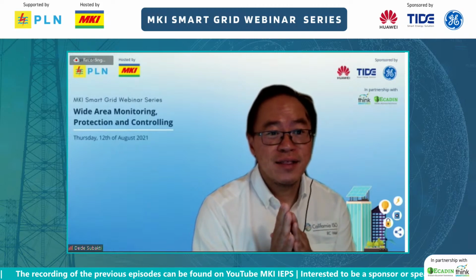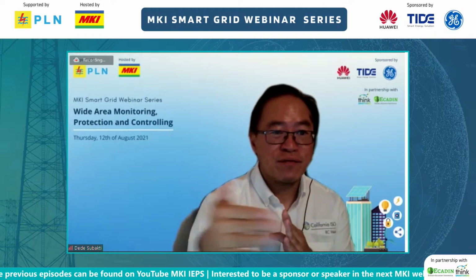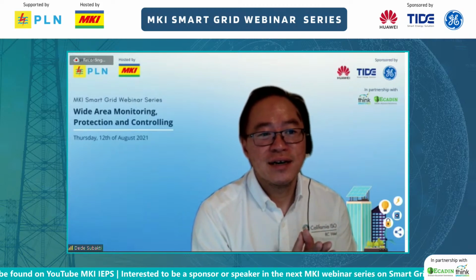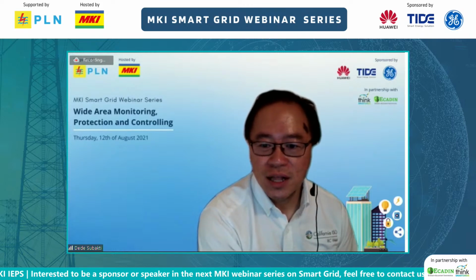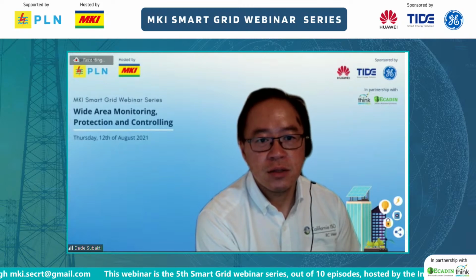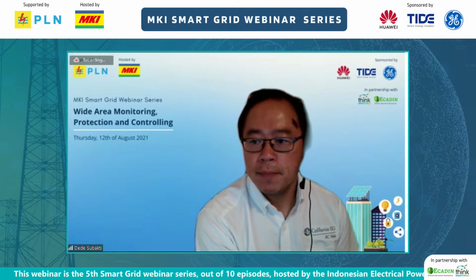We do have a number of dynamic line ratings. The problem with dynamic line rating is that the transmission lines in California are often pretty long, and when they go that long, they go through a lot of different terrain, zigzagging and stuff like that, just kind of like being in Java. So it's a little bit challenging. But most of the solutions we have to put in a lot of this renewable and avoid curtailment is utilizing the remedial action scheme, in which case generation would only get dropped if there is a contingency.